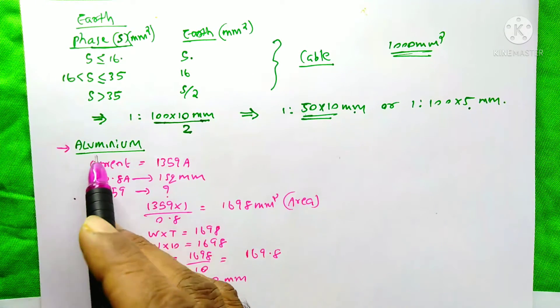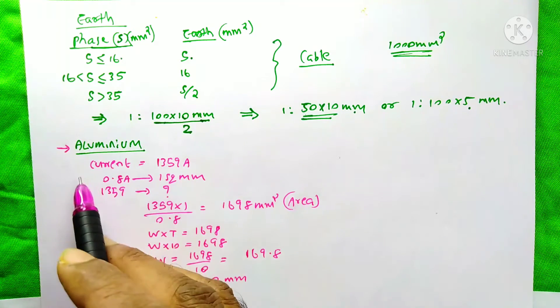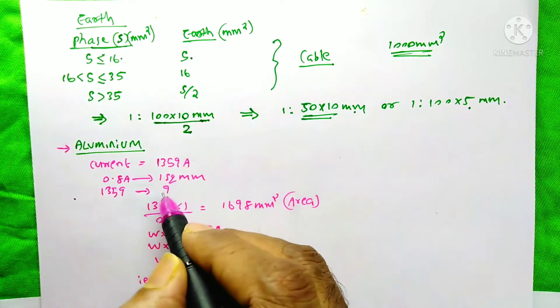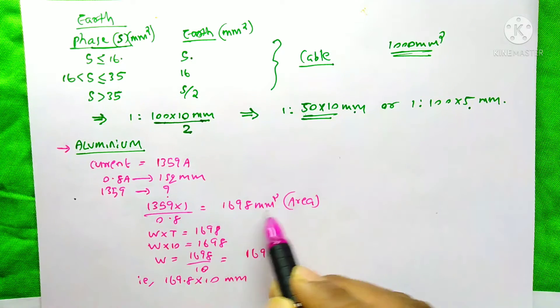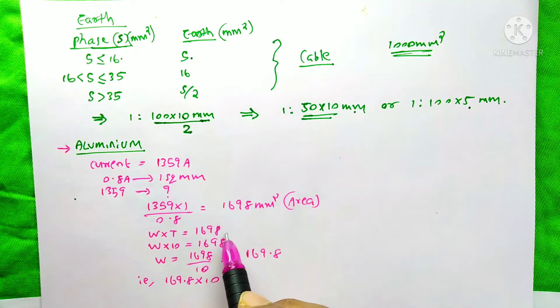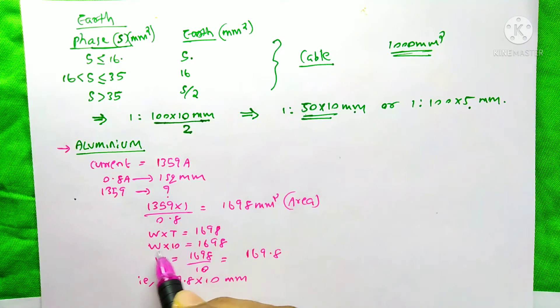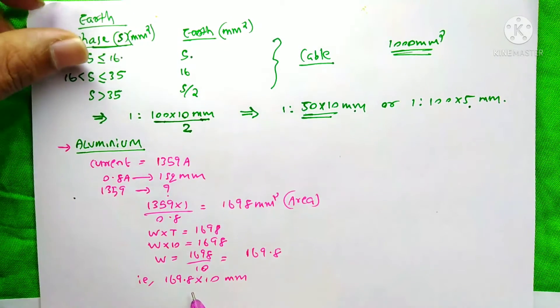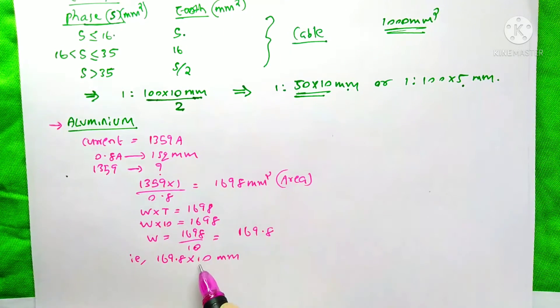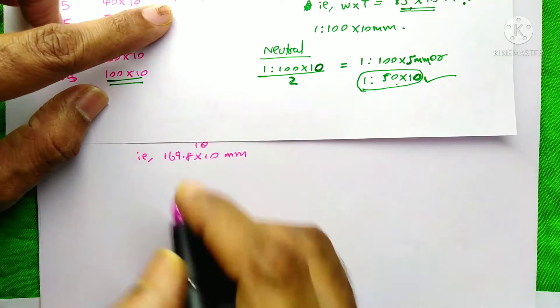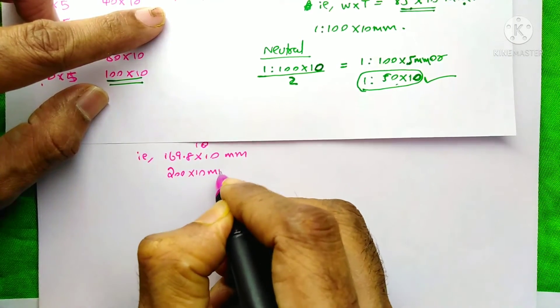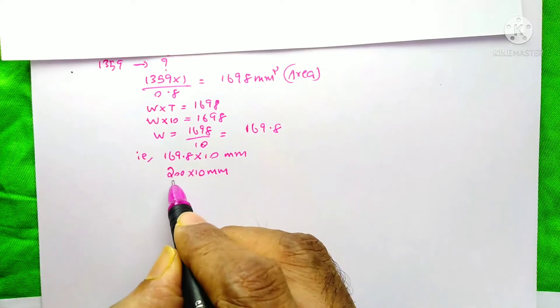For the previous example using aluminum instead of copper: 1359 amps requires 1359 × (1/0.8) = 1698 mm² of bus bar area. Fixing thickness at 10 mm, the width = 1698 / 10 = 169.8 mm. Checking the table, 169.8 mm is not available; the next size up is 200×10 mm, so we select 200×10 mm.